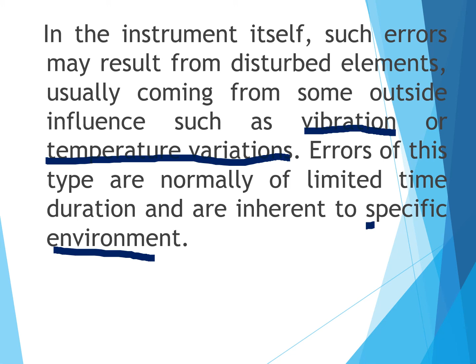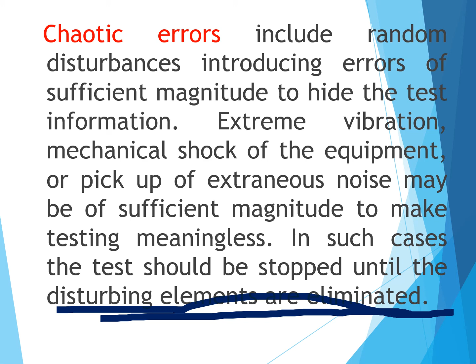As the name implies, illegitimate errors should not exist. They include outside mistakes which can be eliminated through careful exercise and repetition of the measurement. Chaotic errors include random disturbances introducing errors of significant magnitude to hide the test information. Extreme vibrations, mechanical shock of the equipment, or pickup of extraneous noise may be of significant magnitude to make the testing meaningless. In such cases, the test should be stopped until the disturbing elements are eliminated.